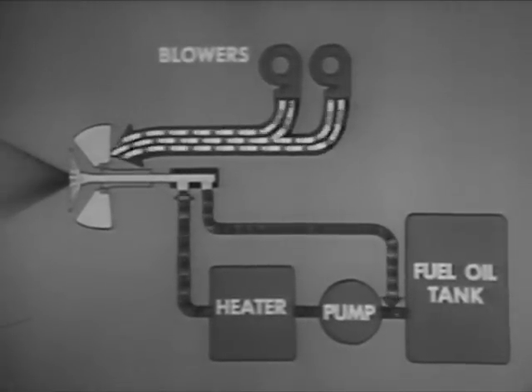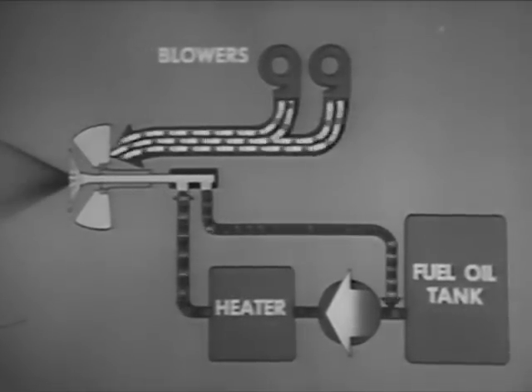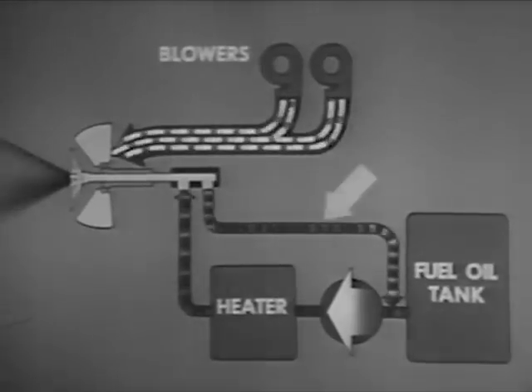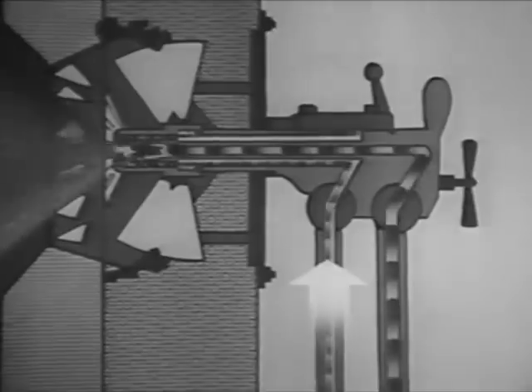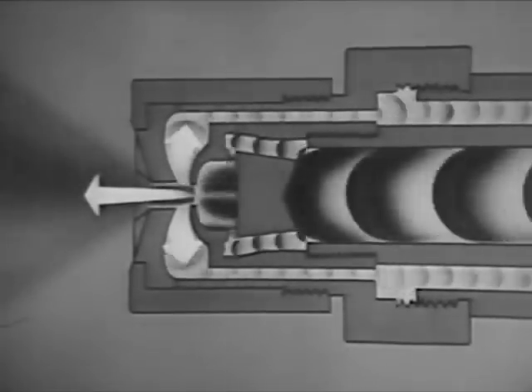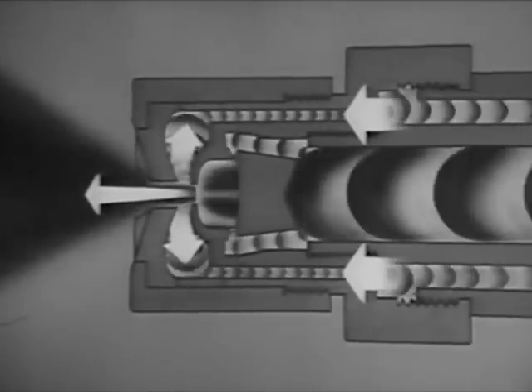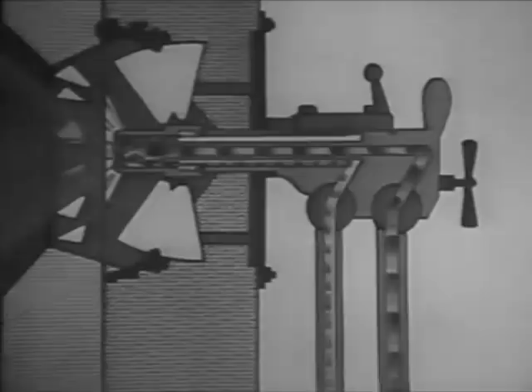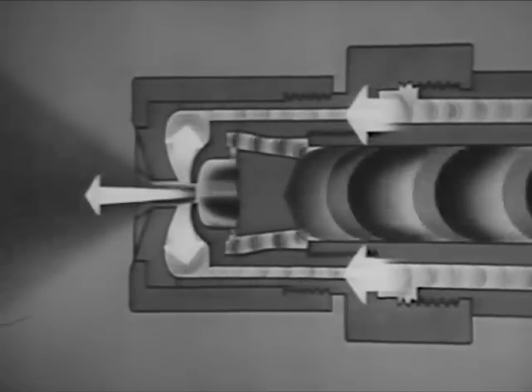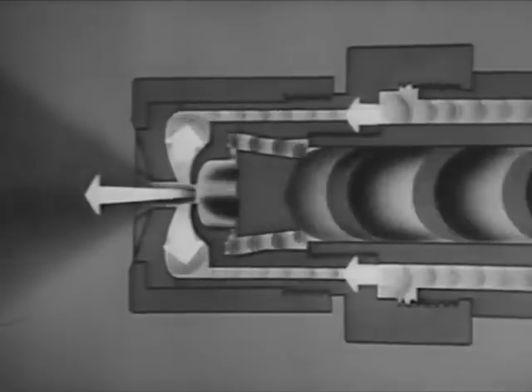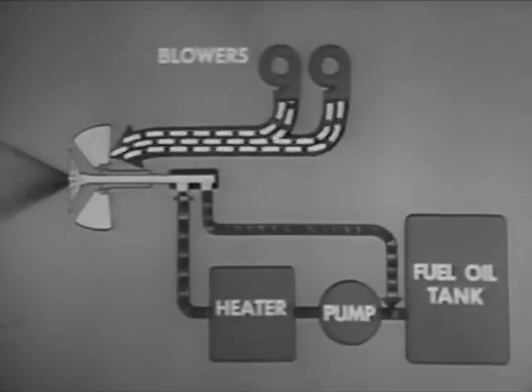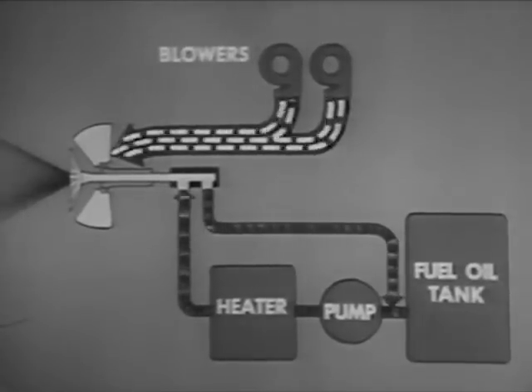In controlling the fuel supply to the burner, you keep the pressure on the oil entering the burner constant and at the maximum for the system. You vary the pressure on the return line. When you close down on the return line valve, less oil can get through. As a result, the pressure builds up in the return line. This greater pressure forces more oil into the furnace than before. When you open up on the valve, the valve passes more oil and return line pressure drops. Less oil enters the furnace. Varying the speed and number of the forced draft blowers is the principal method of controlling the burner air supply.